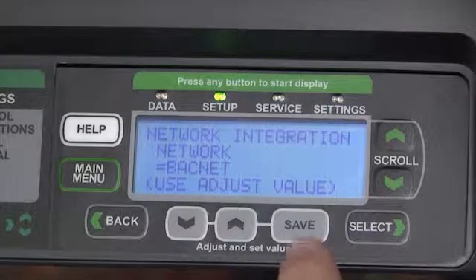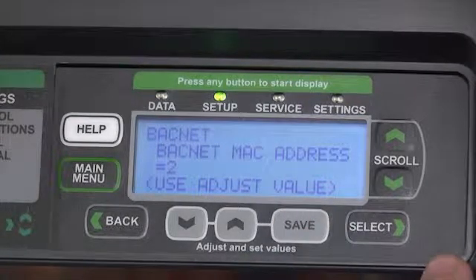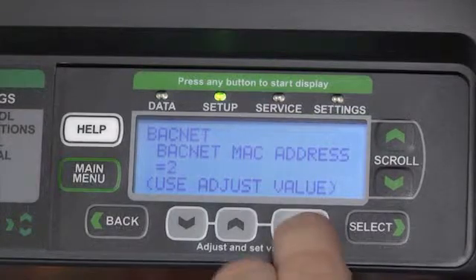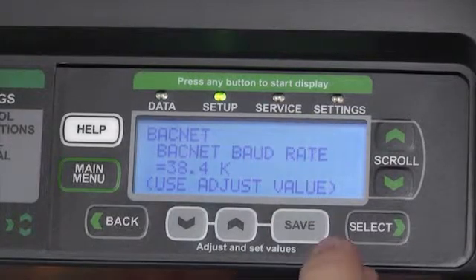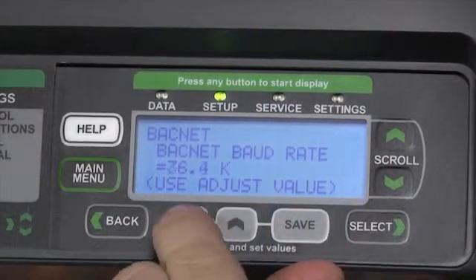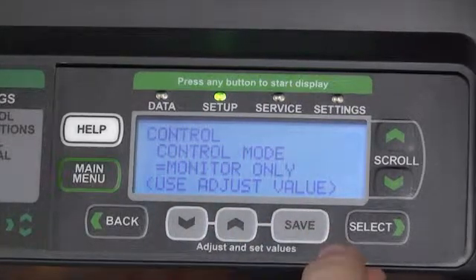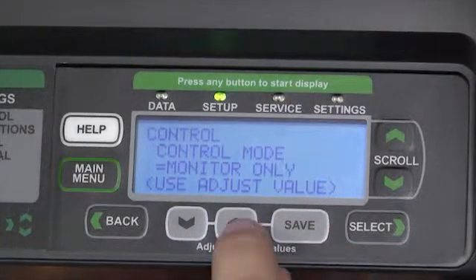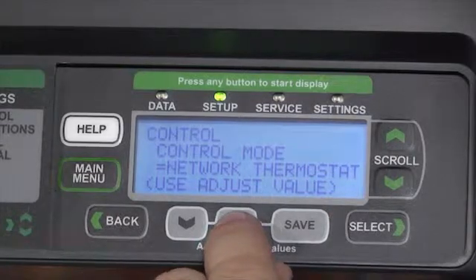Pressing the save button will lock in the value and take us to the next screen, where we'll set our MAC address, our baud rate from the variable selections available to us, and our control mode — whether it's control only, a network thermostat, or a room sensor.